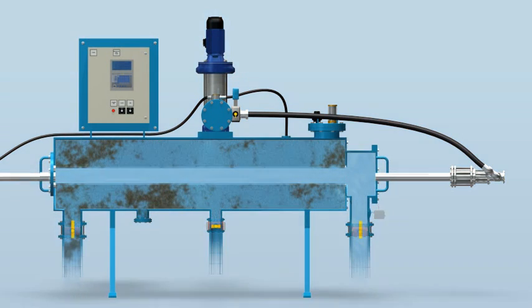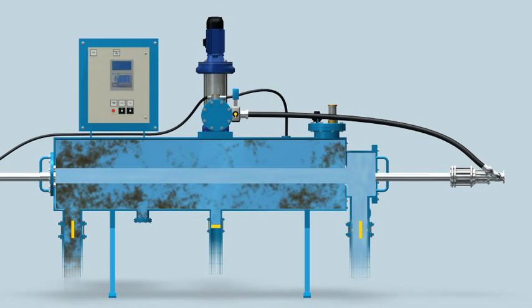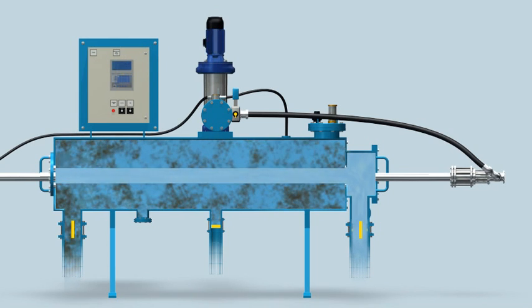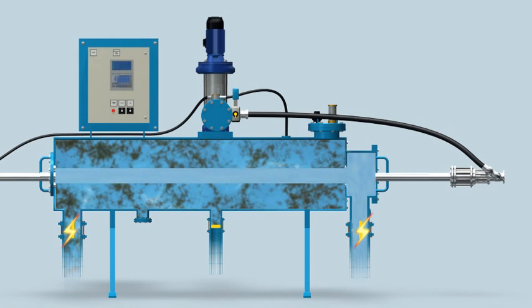The cleaning sequence starts with the control unit starting the flushing pump, which boosts into the system highly pressurized clean water. The inlet and the outlet control valves are then closed, isolating the filter from the main line.